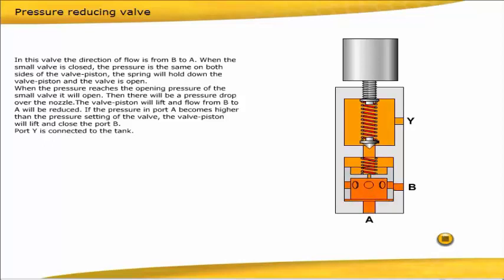When the pressure reaches the opening pressure of the small valve, it will open. Then there will be a pressure drop over the nozzle. The valve piston will lift and flow from B to A will be reduced.